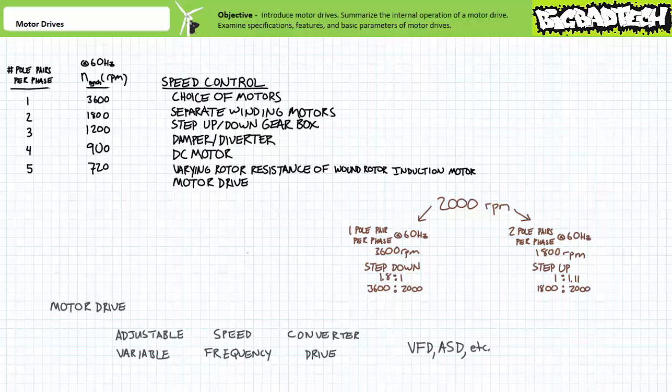All these methods, while effective, are being largely supplanted by the advent of inexpensive and extremely versatile motor drives. Motor drives are known by many names — pretty much pick one of these words: variable or adjustable; one of these words: frequency or speed; and one of these words: drive or converter — string them together and you've got what I'm calling a motor drive. Acceptable combinations include variable frequency drive, adjustable speed drive, or numerous interchangeable abbreviations: VFDs, AFDs, VSDs, or ASDs.